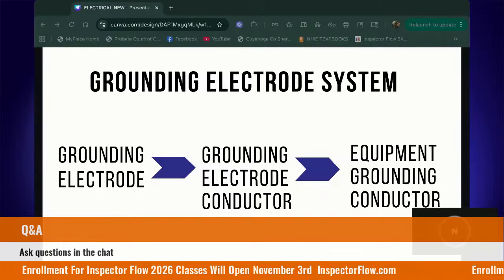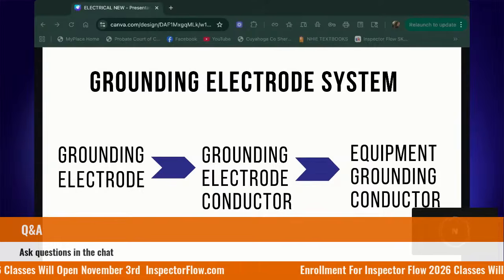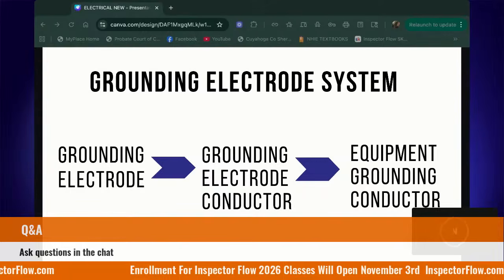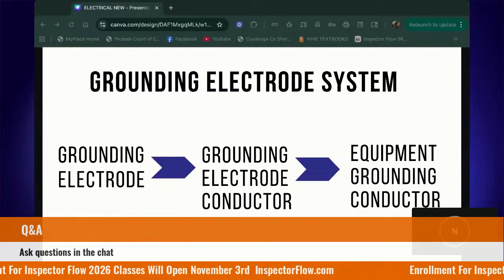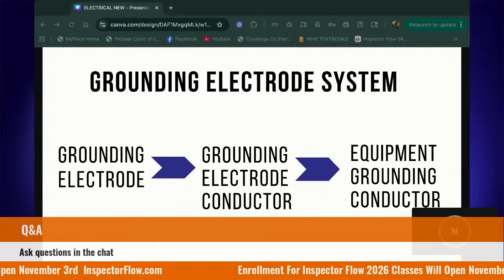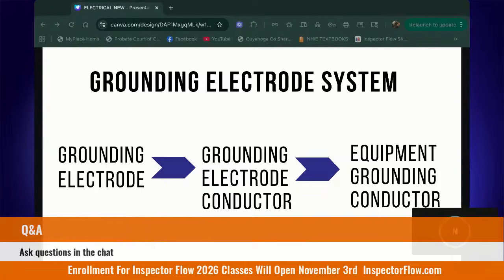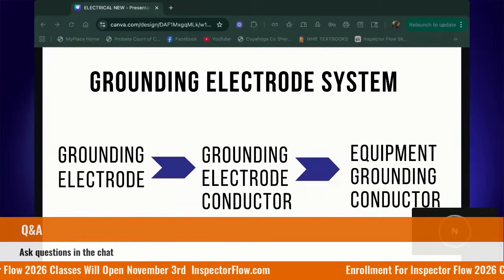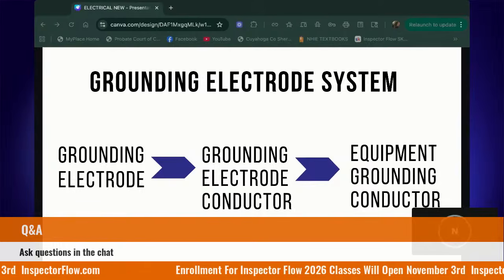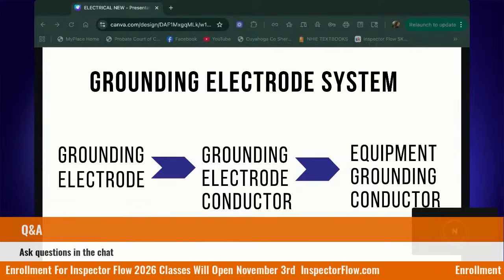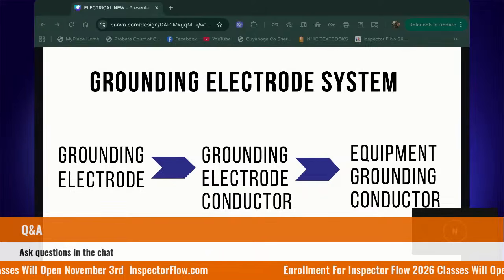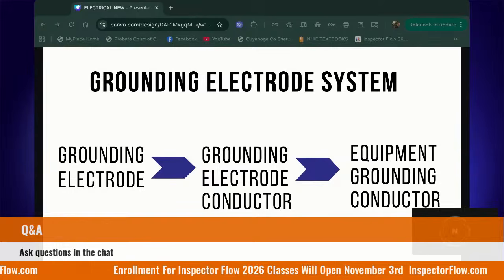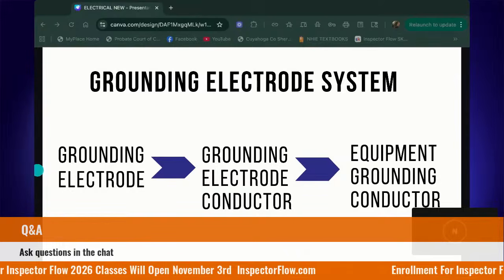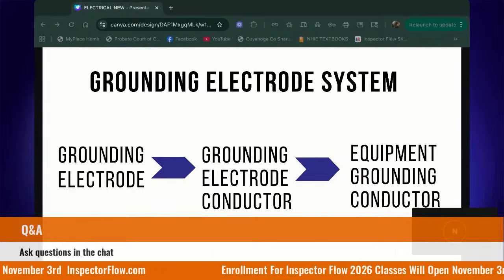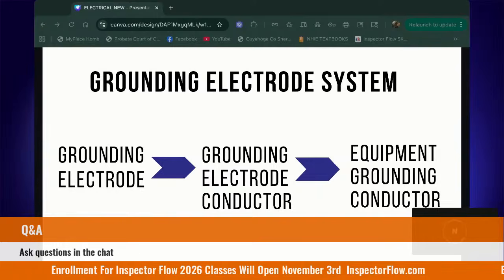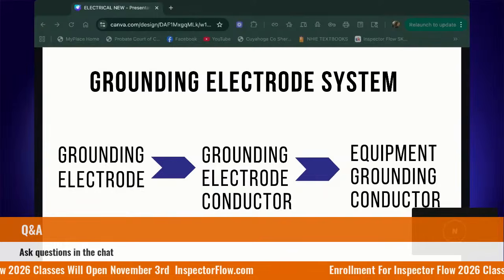So in the main panel, you could have a bus bar that has neutrals, white wires, and ground wires, bare copper or green wires. This would just be a neutral grounding bus bar because you have both. Only in the main panel. Because in the main panel, the neutrals and the grounds are bonded together anyway to allow a path to clear a fault. Does that make sense? Yes, no, maybe so. Yes. Okay.